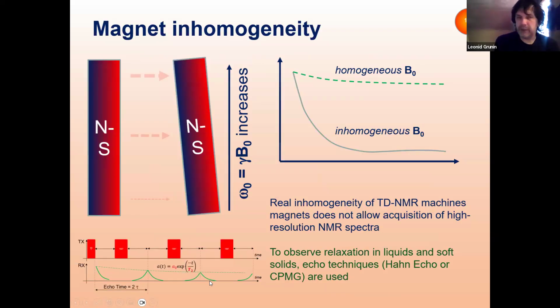The other thing is inhomogeneity. As I already told you, the expensive high-resolution spectroscopy magnet is a perfect magnet. In a time domain NMR device, since it's not that expensive, it normally does not have a special shimming system, and the homogeneity of the B0 field is much lower. But in many cases that is even better, and it gives you much better stability of the signal. The issue of observing direct T2 or T2 star can easily be resolved with the so-called echo technique. So we will talk about echo techniques also today.